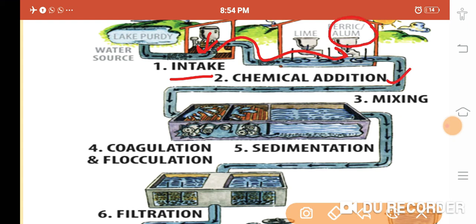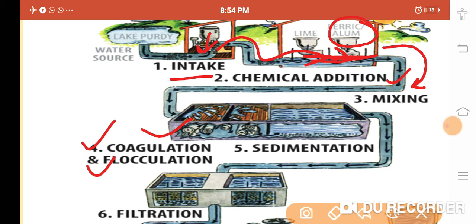In the chemical addition stage, we add ferric salt or alum. By adding alum, the clay particles become dense and settle down as impurity. That water is then passed into another container where coagulation or flocculation takes place. Coagulation means the combination of a large number of particles — when more than two particles attach together, they become dense and settle down.